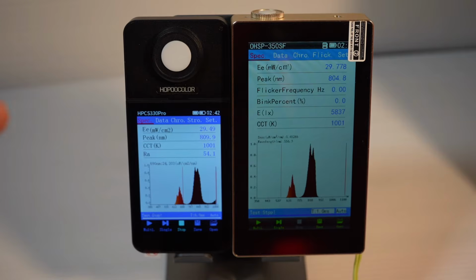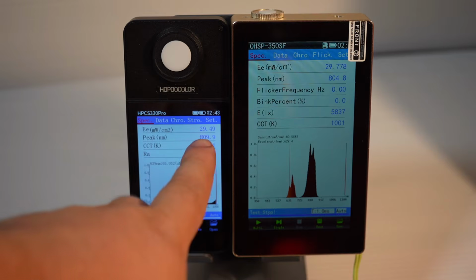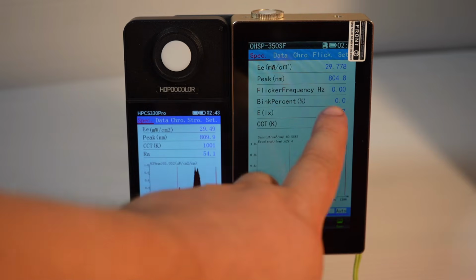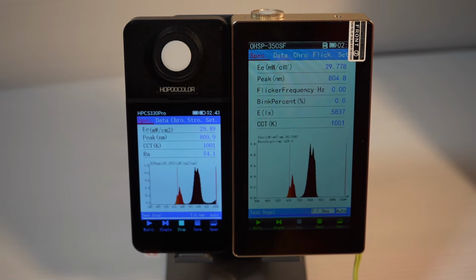so that's where you get the significant savings on price. But according to their spec sheet and some of the warnings they told me, the cheaper one might have a little bit more margin for error on the percentage bars for milliwatts per centimeter squared, or pluses or minuses on the nanometers. But overall, I've been testing it out and it looks like a very close match to the more expensive one. As an example, I took a measurement with the RL Pro 300 from Shenzhen Idealite at 24 inches away, and we got very similar intensity numbers, about 29 milliwatts per centimeter squared for both of them.